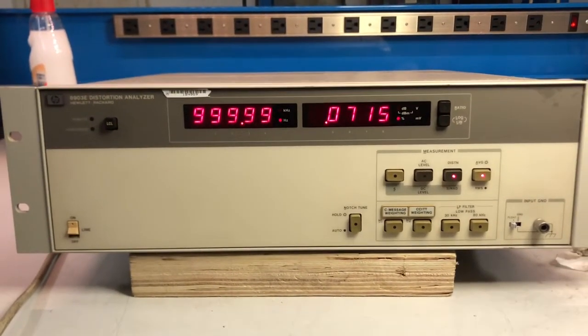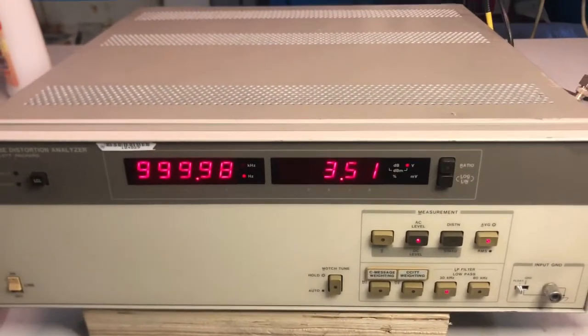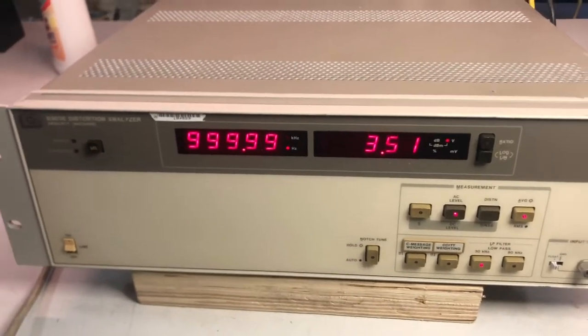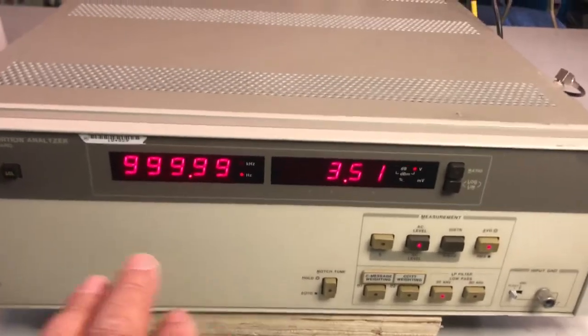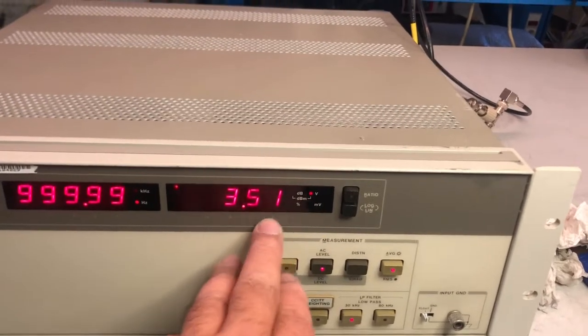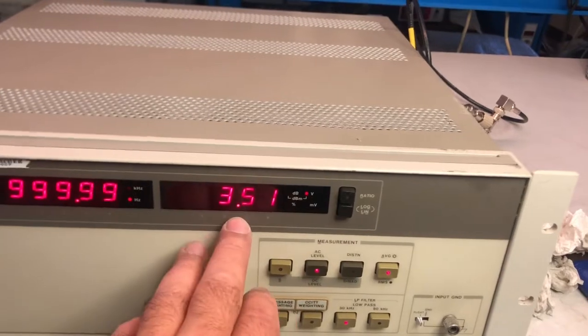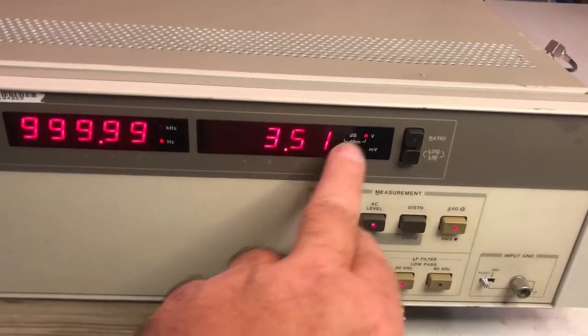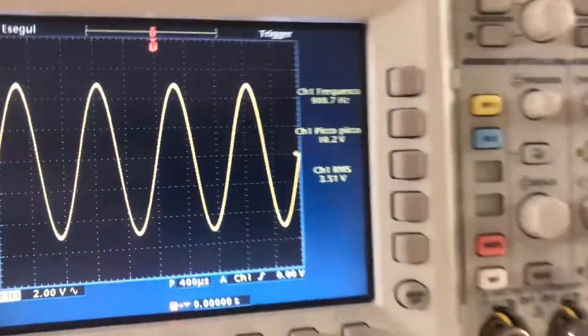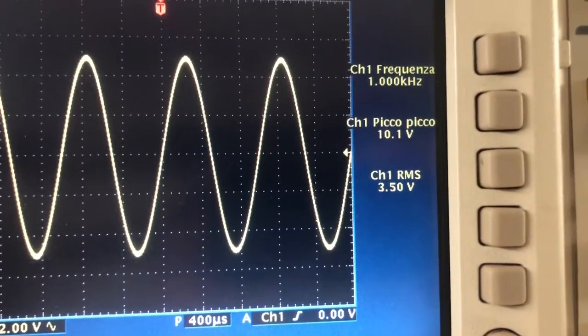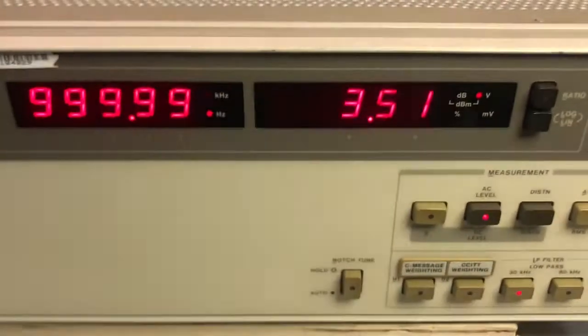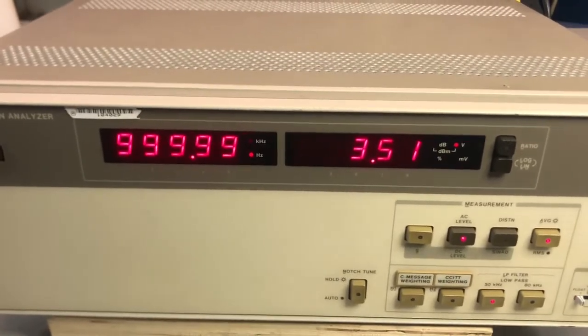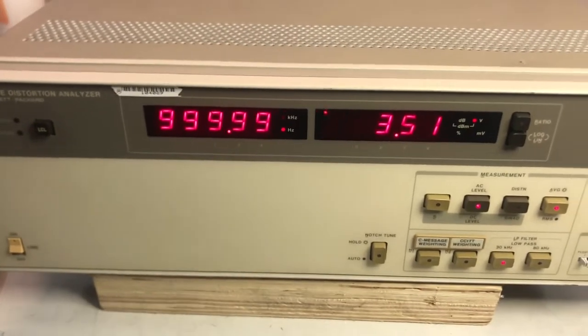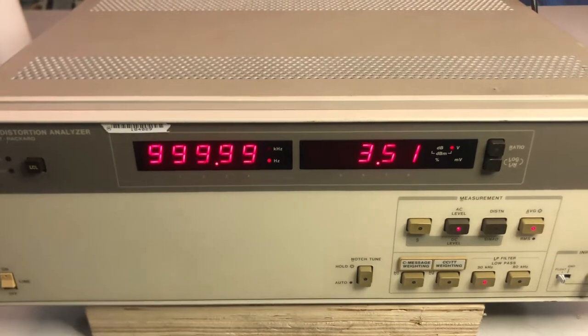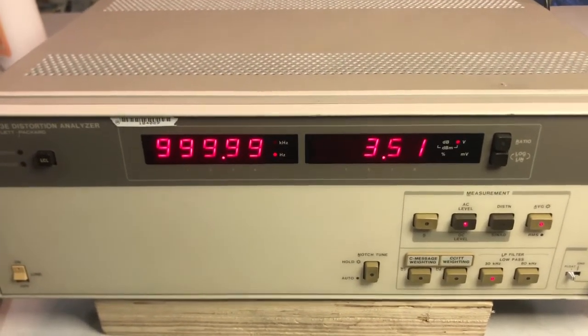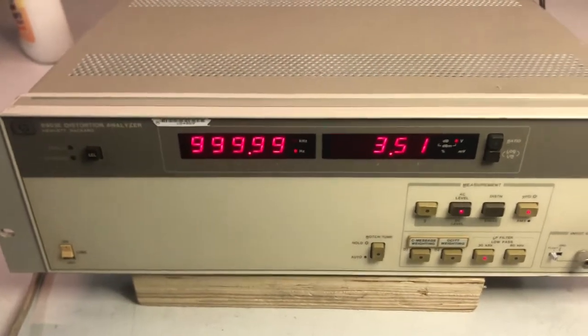Let's try to switch off the output. Looking at the service manual, it seems that it needs some special instruments like an AC calibrator. However, it is required to check the input flatness and the AC voltmeter reading. So I'm having 3.51 volt RMS, and on my scope, which I know is well calibrated, I'm reading exactly the same. I've been told this instrument was pretty accurate, and it seems indeed that it was. So I don't want to mess anymore with calibration right now, and I want to test more in depth with some other instruments.